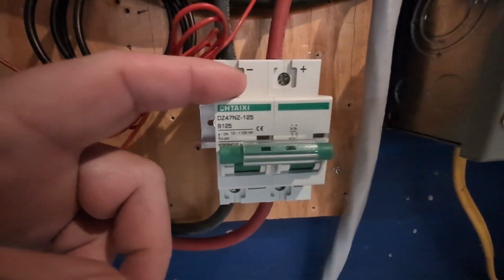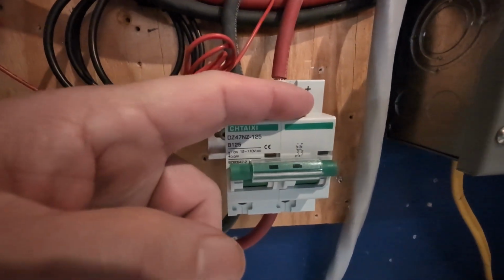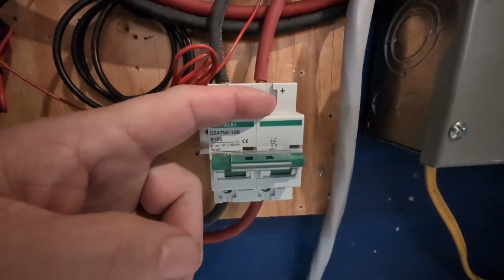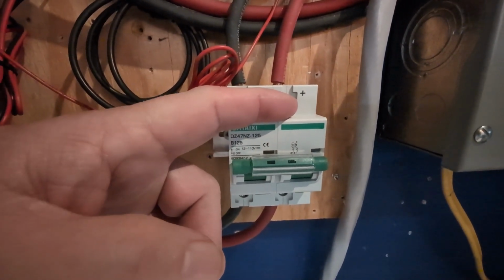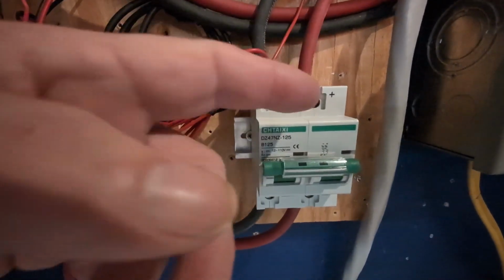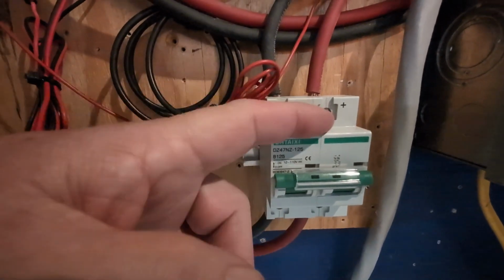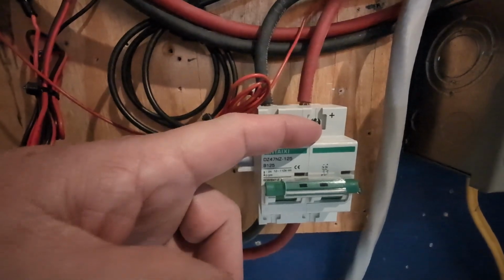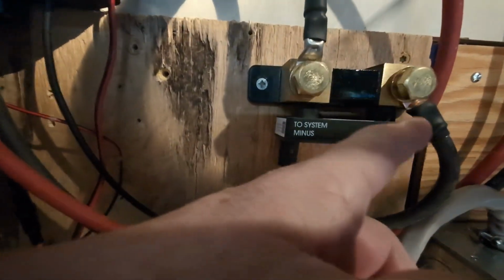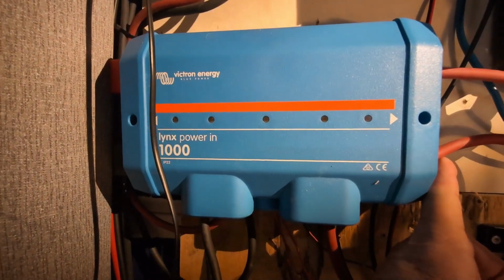And it also has arc suppression, not arc fault protection, because anytime you break a DC circuit and there's a lot of current flowing, there could be an arc that jumps across. So this takes care of that and makes sure it's extinguished. The negative then comes up to the shunt, and then that feeds the negative into the Victron bus bar.